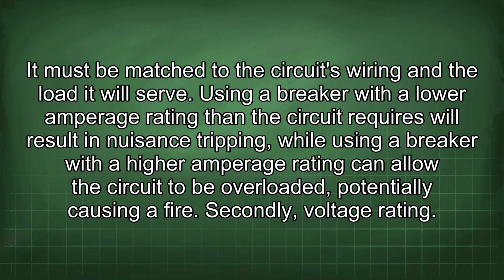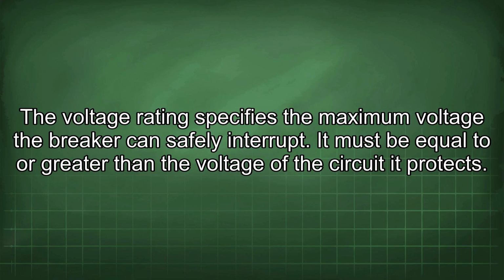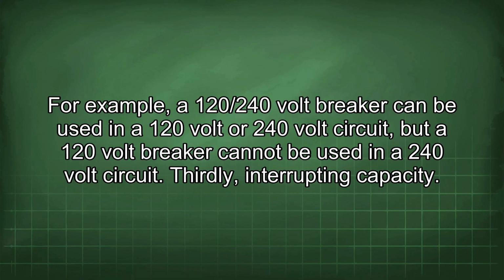Secondly, voltage rating. The voltage rating specifies the maximum voltage the breaker can safely interrupt. It must be equal to or greater than the voltage of the circuit it protects. For example, a 120/240 volt breaker can be used in a 120 volt or 240 volt circuit, but a 120 volt breaker cannot be used in a 240 volt circuit.